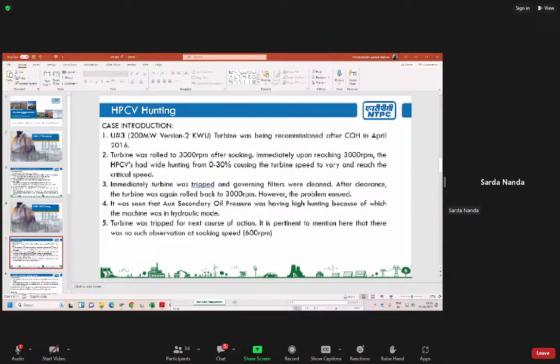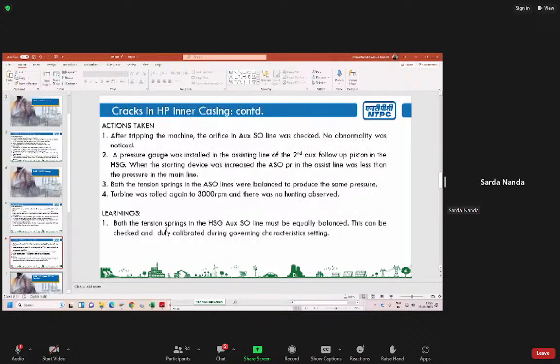How do we check that? We took a pressure gauge and put it in the assisting line of the second follow piston. And we found that the two pressures were not balanced. We balanced both the pressures and then everything was fixed. But the question is, why did this happen? Why were the two pressures not balanced? Generally, when we are setting the auxiliary secondary oil pressure, we tend to use only one follow piston. We get the pressure and we forget it.